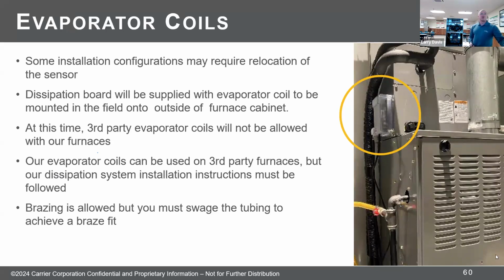Oops, I always forget to reset that. As of right now, our outdoor units are not rated with third-party evaporator coil or our furnaces because we don't know how they're doing their dissipation control. So we can use our outdoor unit with our evaporator coil and a third-party furnace because we're using our dissipation system. So that's really what the difference there is, who's running the show as far as dissipation goes and how it's done.